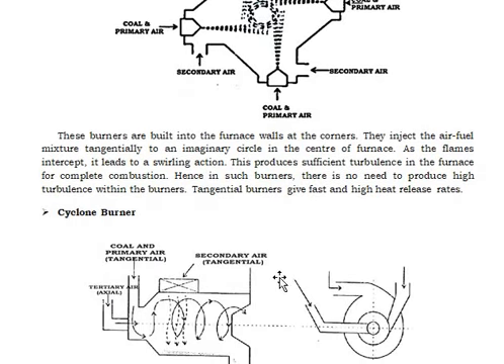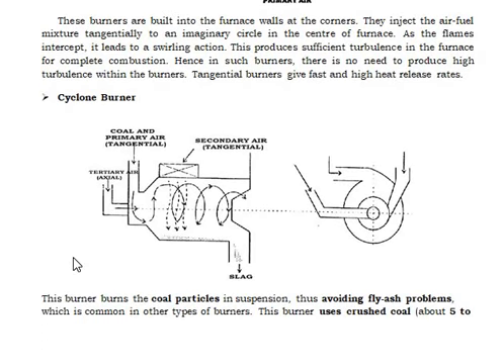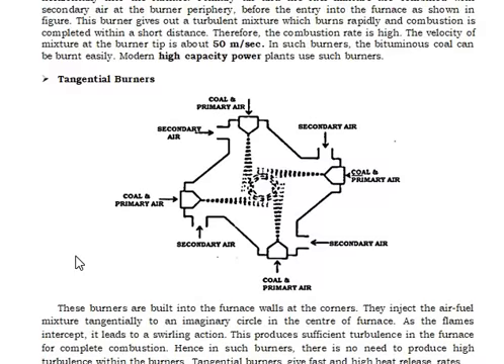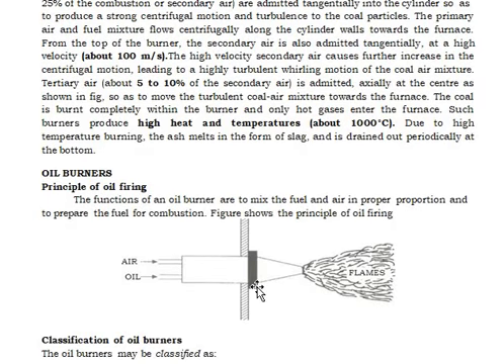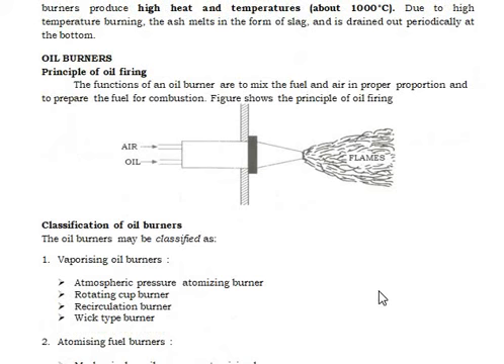Tangential burners give fast and high heat release rates. The cyclone burner — you can see it in the figure — burns the coal particles in suspension, thus avoiding fly ash problems which are common in other types of burners. The burner uses crushed coal. These are also the oil burners: the principle of oil firing and classification of oil burners, including vaporizing oil burners, atmospheric pressure atomizing burners, rotating cup burners, recirculating burners, mechanical or oil pressure atomizing burners, and high pressure air atomizing burners.